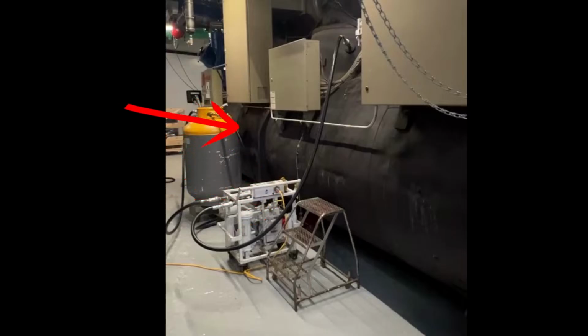We should be monitoring our weight, and having sight glasses is ideal here at the recovery cylinder itself, so that we can make sure that we're not accidentally having liquid come back. These particular styles of recovery machines are not made to process liquid refrigerant whatsoever, like we do with, say, a G5 Twin or a Navac recovery. Those can actually process some level of liquid if you use them correctly. Okay, using them correctly is a big caveat there, but these are not. So you've got to make sure we're being cautious of that.